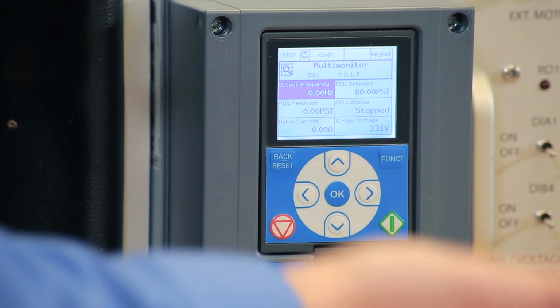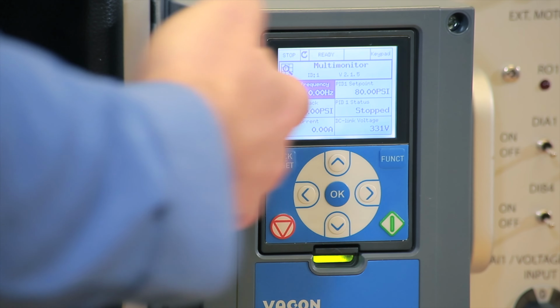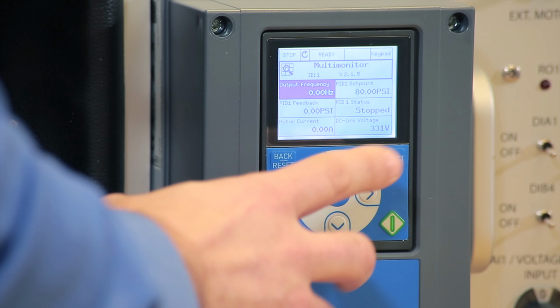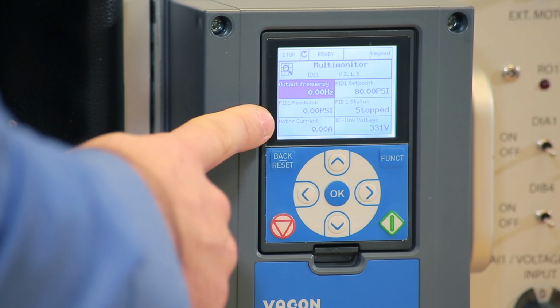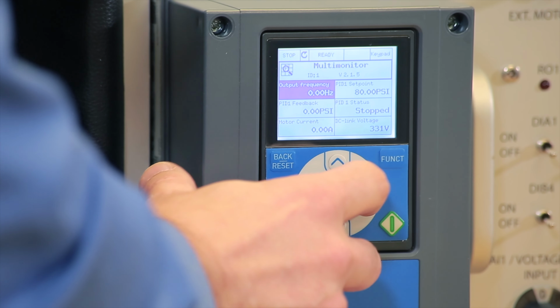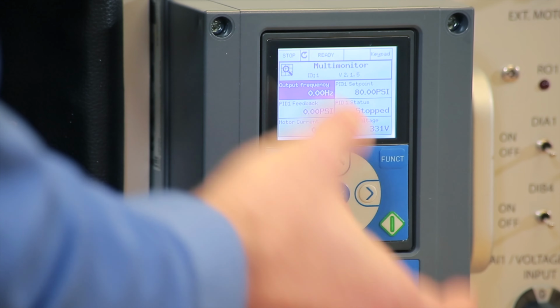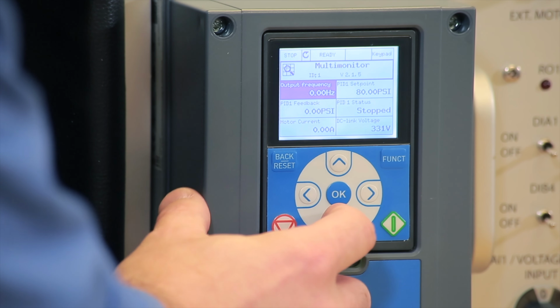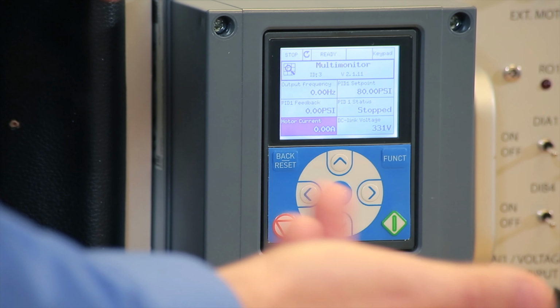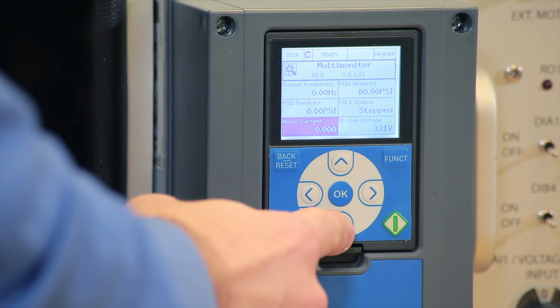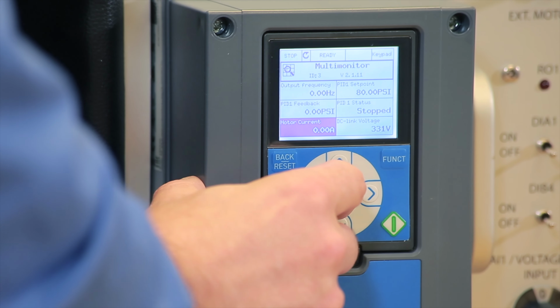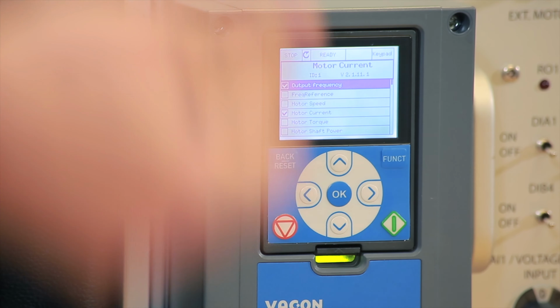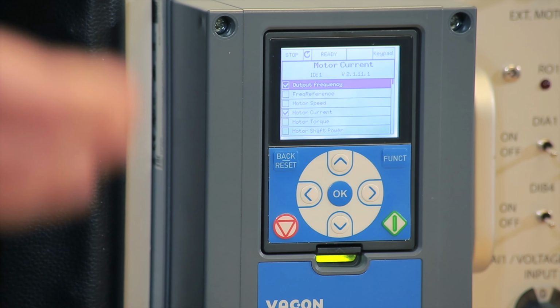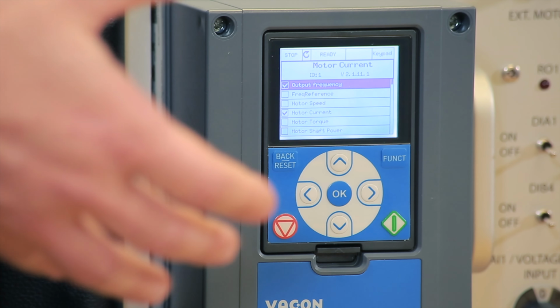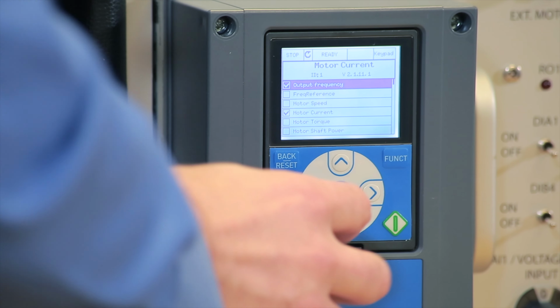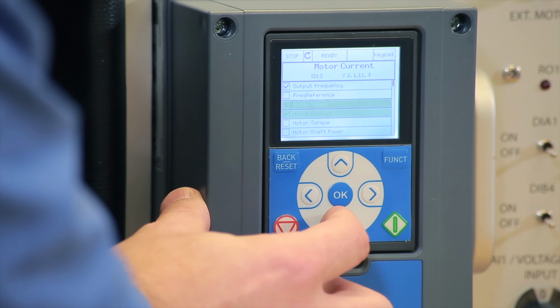But if you want to monitor something else or something additional, such as digital inputs, you can select a value that you do not need. For example, we can select the set point, or output frequency. Just for this example, we can choose motor current, because this motor is so small, we don't care for it really. So we highlight the area that we want to change. You press OK, and then the drive gives you a list of values that you can actually monitor. It's very user-friendly, and it's right there. You highlight what you want to change, and you scroll down to whatever you need.